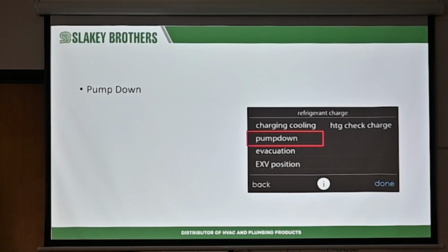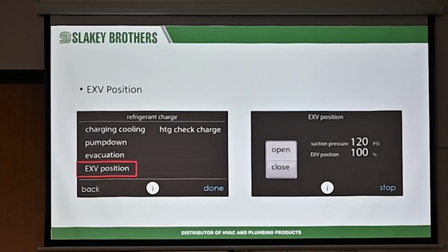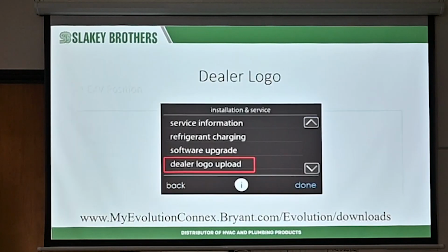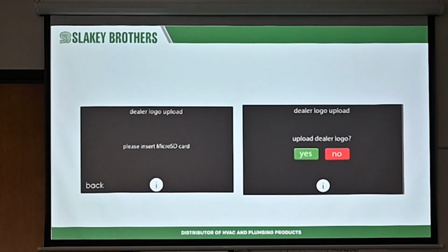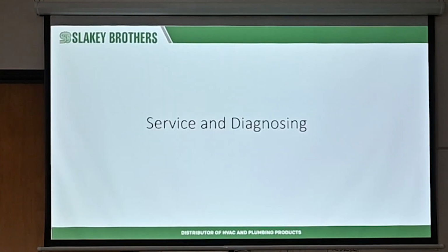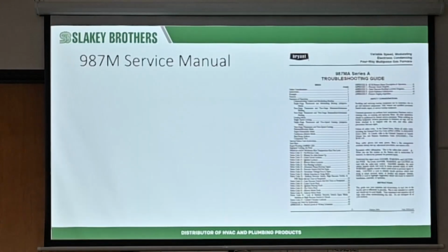That makes evacuation nice and easy so that no refrigerant gets trapped, so you don't shut it down and all of a sudden your pressure starts rising, making you think you have a leak somewhere. Okay? And EXV position, you can get in there with a check on it and look at it, but honestly, you never have to really mess with this one, because if you're evacuating or pumping down, let the machine do its work on its own. The EXV is an electronic expansion valve. You can install a dealer logo. If you have something on the micro SD card, you install it using this little feature here.